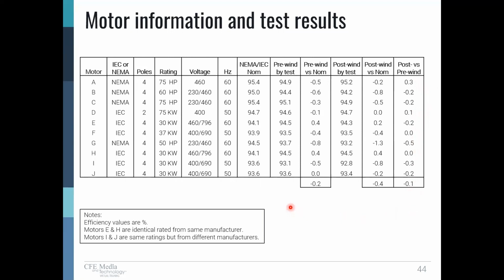Sometimes, again, going back to my days working in a service center and selling electric motors, you know, can we believe the manufacturers, that the nameplates meet what they say they have? Well, pre-rewind versus nominal, this is the manufacturer's changes. They're within 0.2% of what they're saying their efficiency should be. So it says, can you believe the motor nameplate? I think, to be honest and fair to the manufacturers, yes, you can. By the way, all of these values are efficiency values in percent.